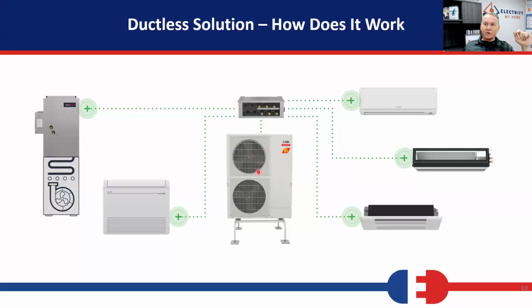And then that extra refrigerant, because this thing can't slow down that far, is going to be fed into the next units in the channels. So if I've got multiple channels on the outside of here, if I can't get all the capacity I need out of the first channel, it's going to send refrigerant into the next channel. Which means I've got a unit in another room that is either getting hot or cold, but the fan isn't running because it's not calling for heating or cooling. And then I've got to go to a third one potentially.